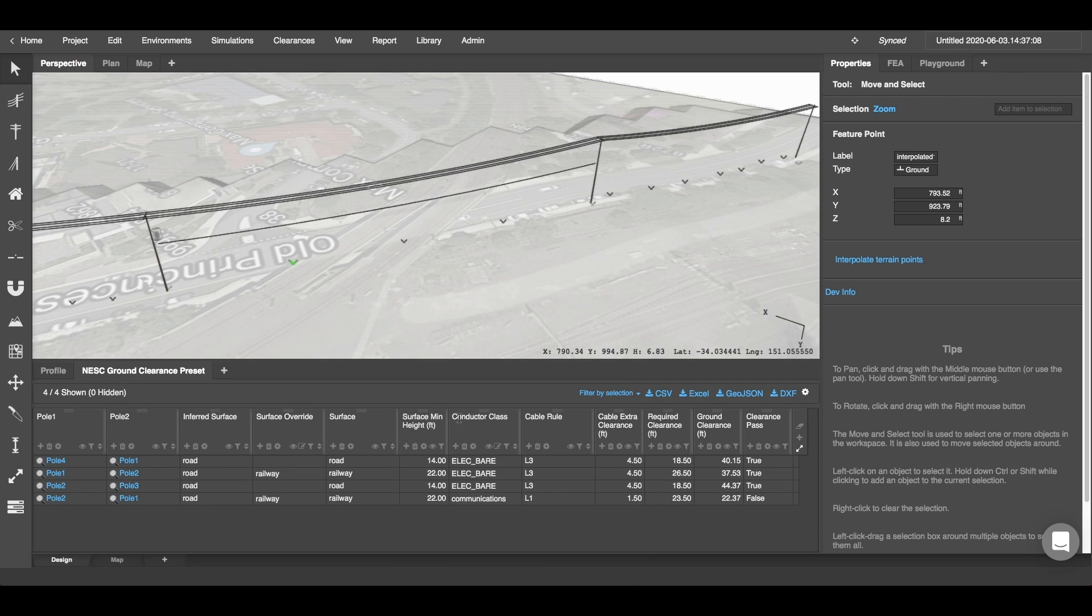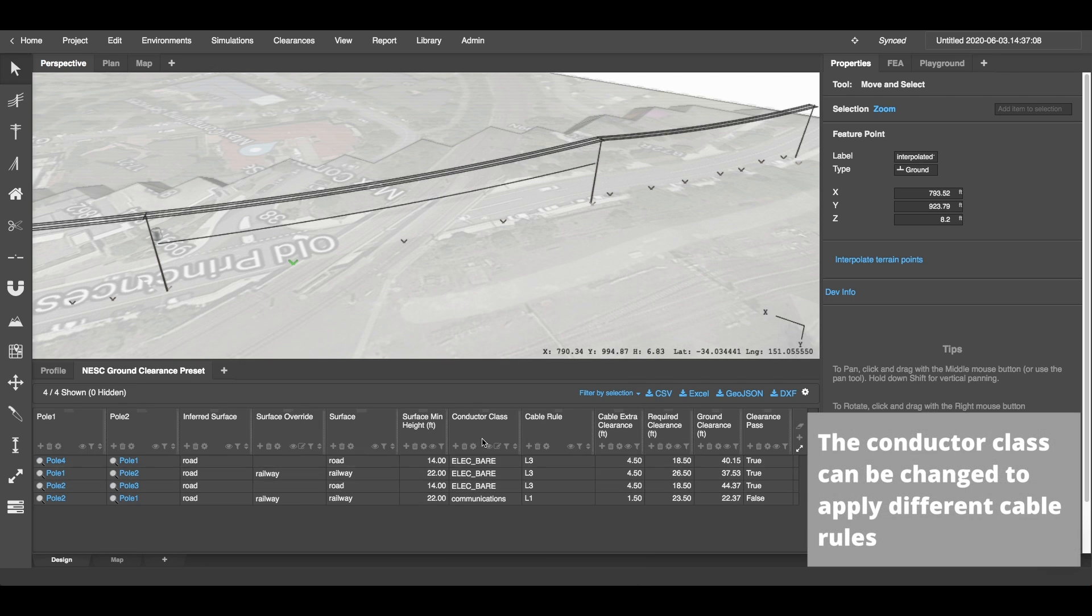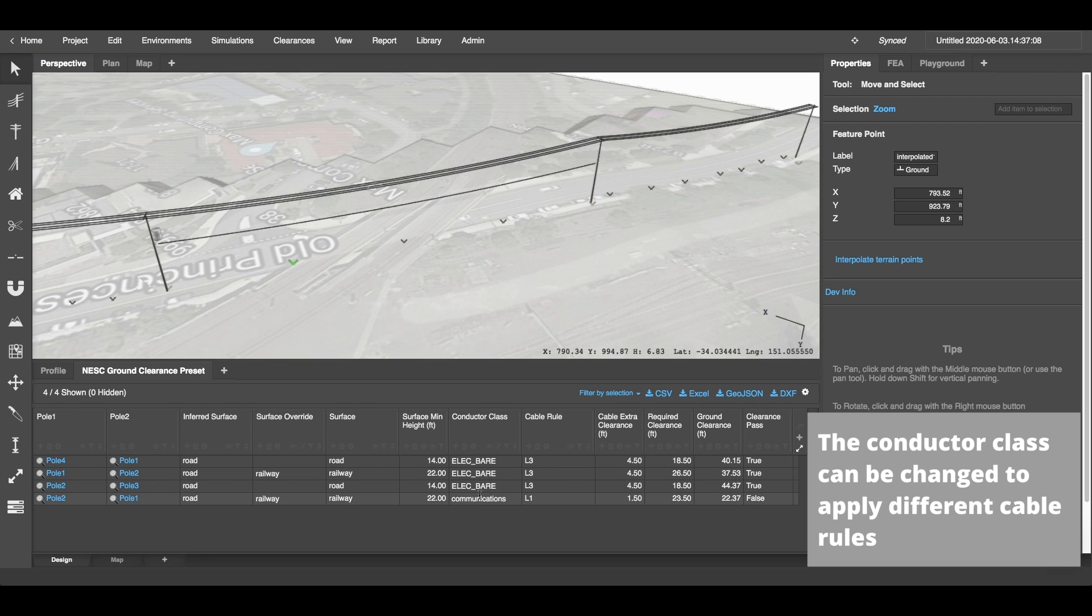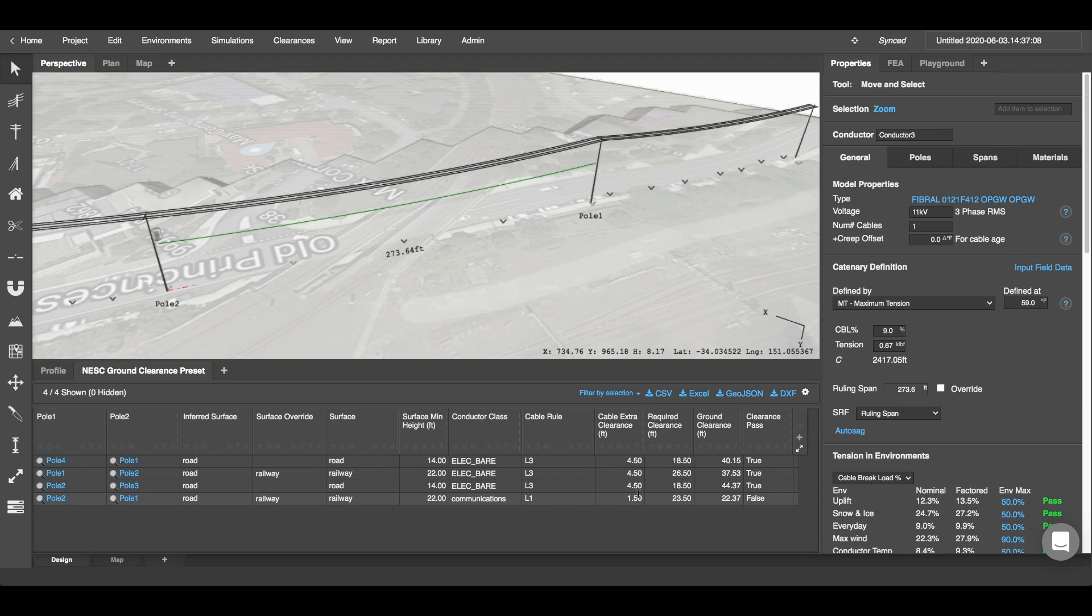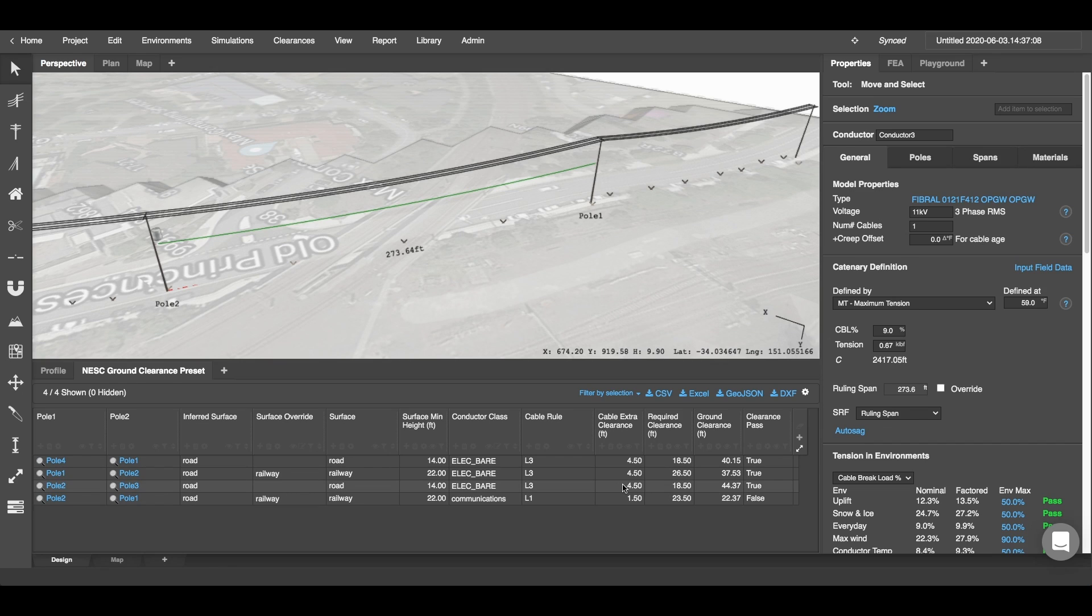Now the next column is our conductor class column. This is where we can change the conductor class to apply different cable rules. You can see that I've already changed my conductor class between Pole 1 and Pole 2 because this conductor here is a communication cable. So I've just typed in communications here and that's applied the cable rule L1, which has a cable extra clearance requirement of 1.5 feet. However, all the other conductors are electric and so they have an extra clearance requirement of 4.5 feet.